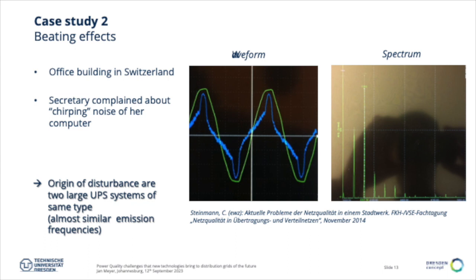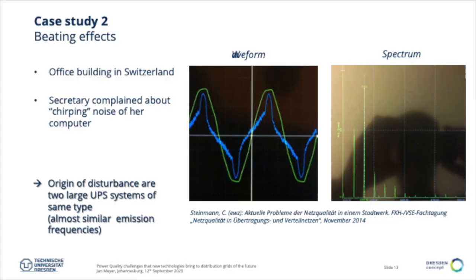It finally was caused by 2 large UPS systems also utilizing an active front end, same make, but the switching frequencies, due to manufacturing tolerances, will never be exactly the same. So you get the beating effect, which I will explain on the next slide, where we observed something similar in a car charging infrastructure. So imagine we have a low voltage network here. We have a bus bar or a junction box where 4 charging stations with 2 charging points each are connected.